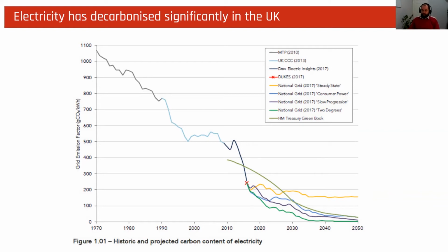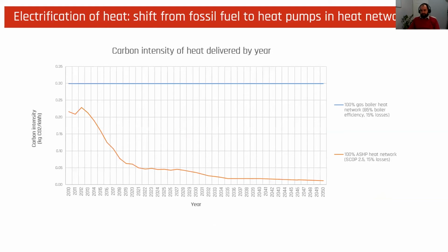And what that means from a heat generation perspective is that heat pumps, so this graph shows the carbon intensity of the heat delivered to a resident with some assumptions. So the blue line is gas boiler, so you've got natural gas going into the boiler, 85% efficient, which is a good rule of thumb. And then you have 15% losses on the heat network. That effectively means you're delivering a carbon intensity of heat of about 0.3 kilograms.